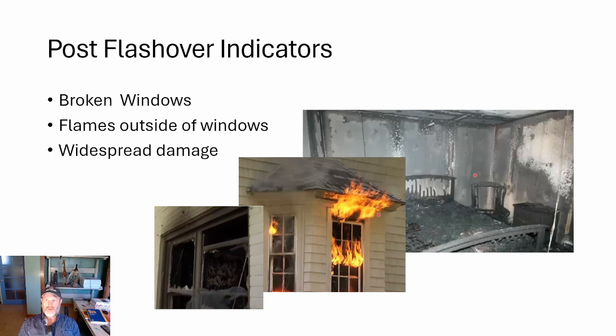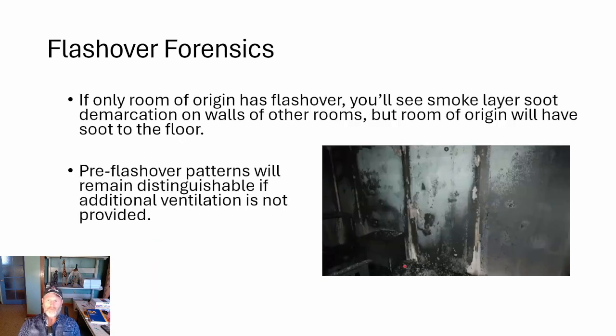So it really drives home the importance of understanding the facts around a case through testimony and witnesses prior to arriving at a conclusion. So this is a famous test, and the point I wanted to bring up here is that you're going to have very distinctive soot layers pre-flashover. So while it's still a material limited or combustible fuel limited fire, you'll have clearly demarcated patterns.